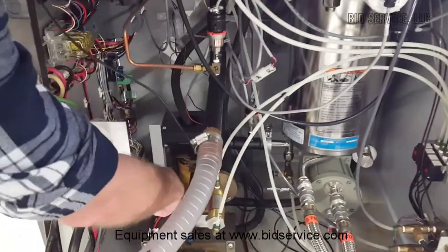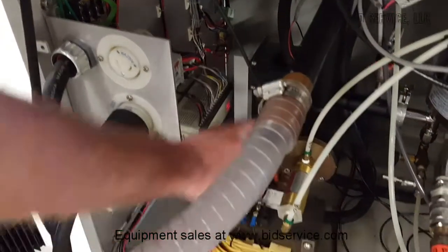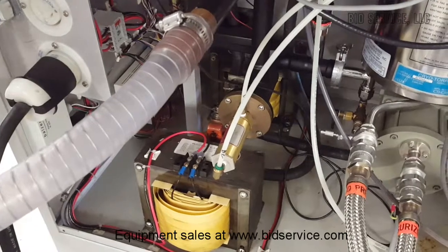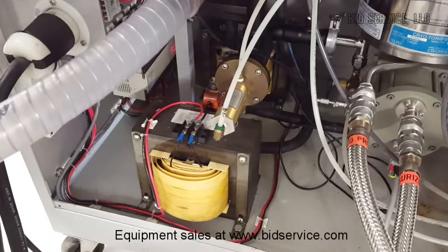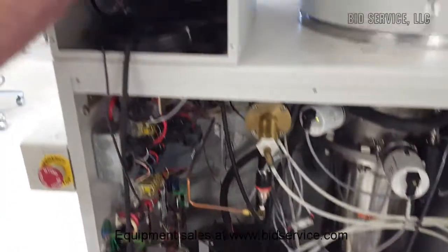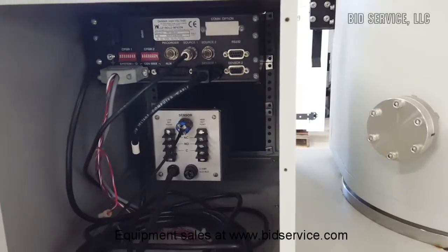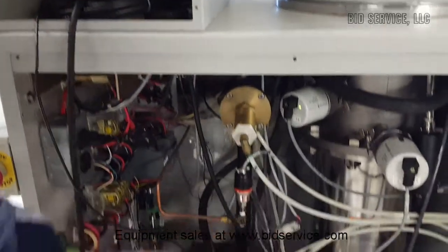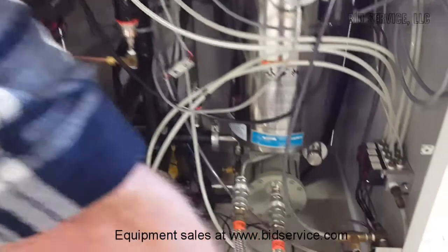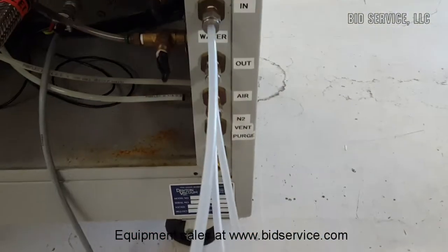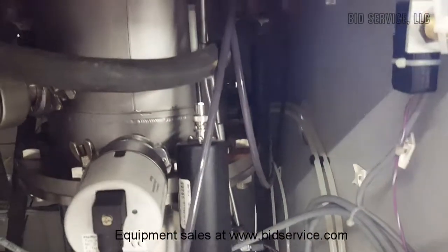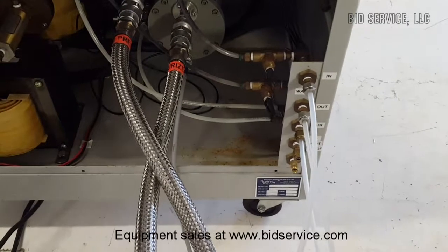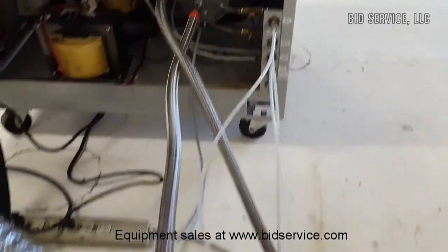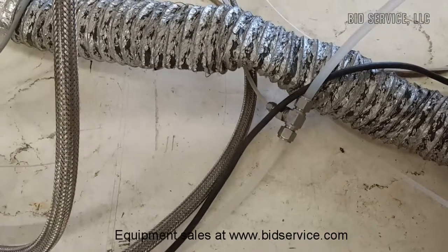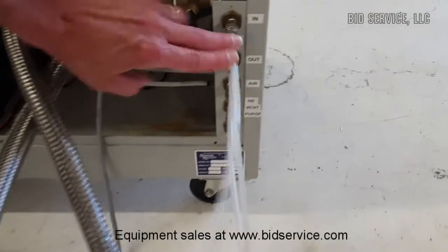And just quickly down here, there's a PLC being used in this unit. Here are your two kVA transformers. There's thermal elements, filaments. And back here is the back of the Inficon and your temperature controller, or your temperature monitor, which gets connected to the cryo pump. And again, you're going to have water lines coming in, and they're being used to cool your feed throughs, your high voltage, your high current feed throughs on either side. So you have an in and out, supply and return. The way I have it set up is I have it keyed into the 2 lines going over to the compressor. Down here, we have it keyed in 1/4 inch line. So it's marked here, water in and out, 1/4 inch line.